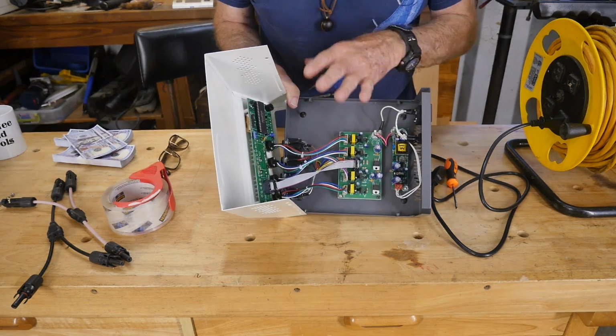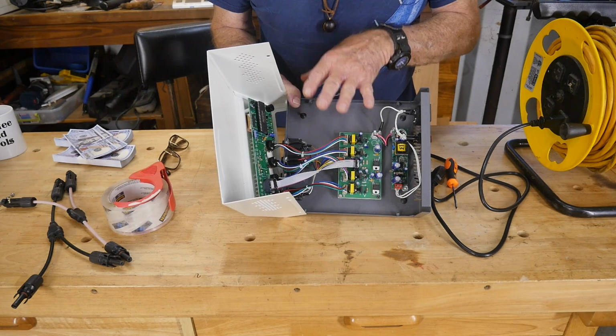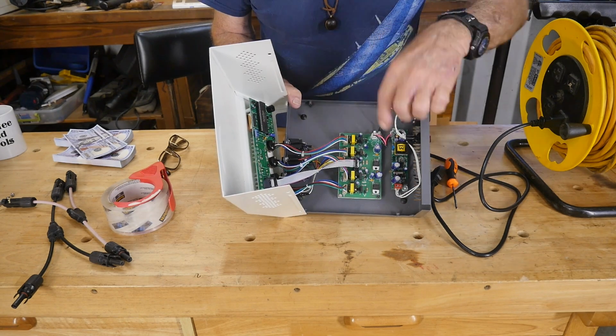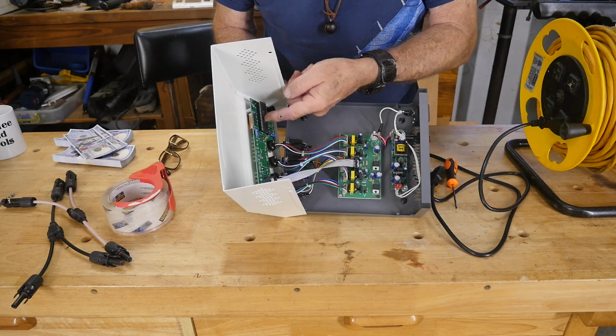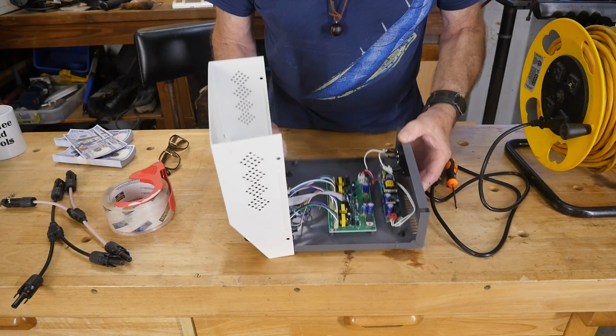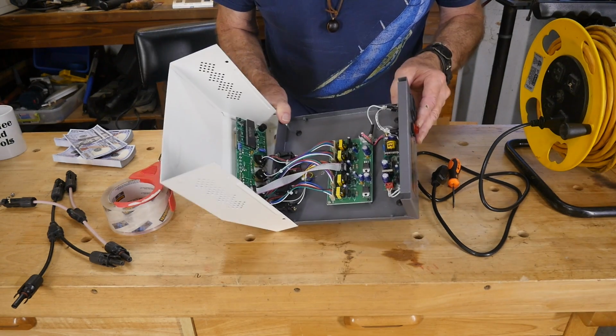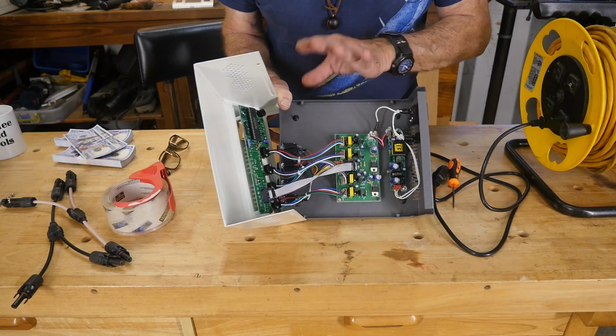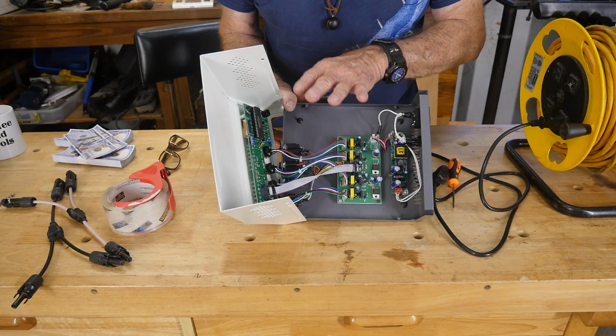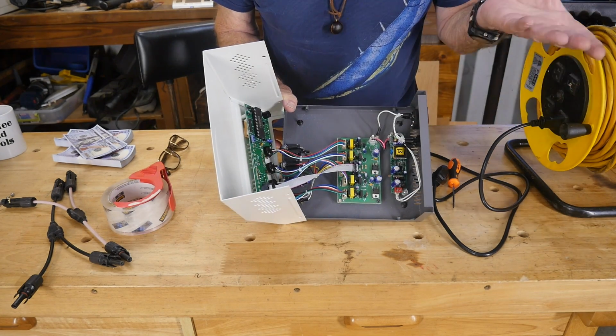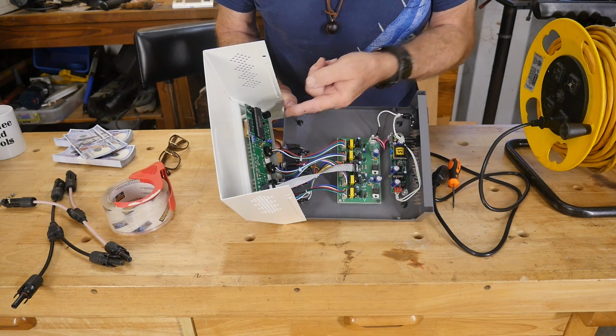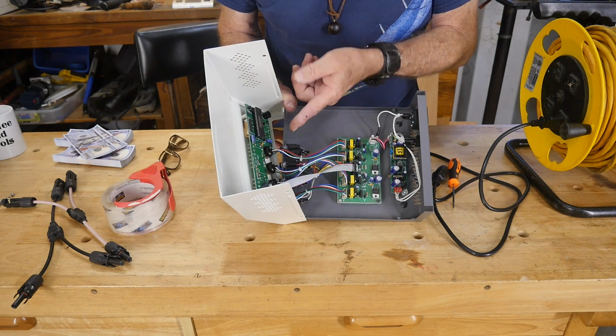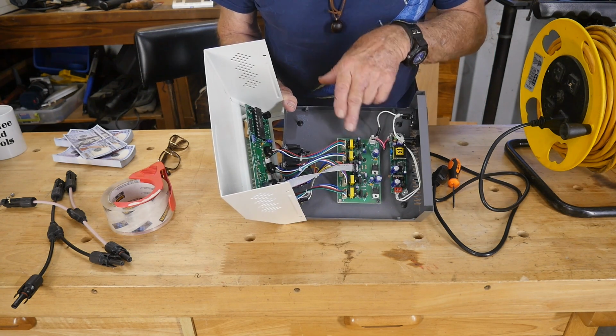Basically, this thing has probably been hit by a lightning strike, and it's been surged, and it's gone right through, and everything's toast in here. So at this point, there are no replaceable parts to the component. Unfortunately, this is where we stop and call it a dead end on this one, because we can't go any further. The chip probably needs to be replaced, but there could be other damage in the board itself.